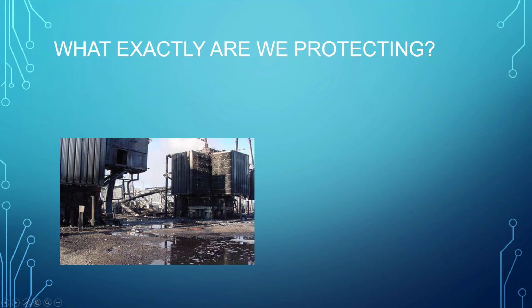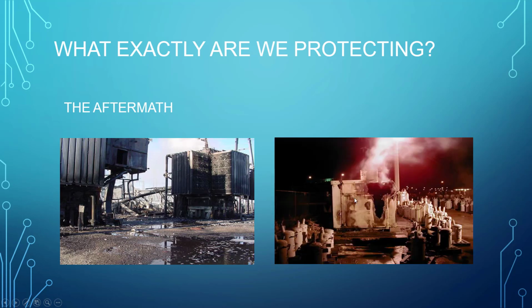If it happened, you don't want it to spread to other sections of the substation, because in a substation, usually the setup you have there, you might have 3 different levels in one substation. So you've got a high voltage, a very high voltage, and a medium voltage. So if you have a fire in your high voltage section, you want to isolate the other sections, and vice versa. As you can see here, this transformer completely ripped apart because of a fire.